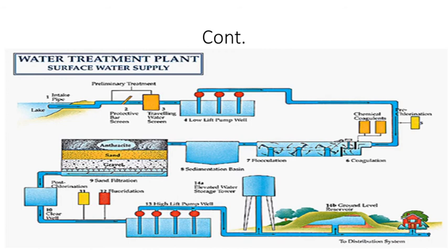The mechanism of filtration, or the action of the filtration process, has 3 to 4 steps. First, mechanical straining, where the suspended particles cannot pass through the bed of sand. Next, sedimentation, where the voids are present and suspended particles settle down. And biological metabolism, where oxidation takes place. So that is the process that actually happens in the filter.